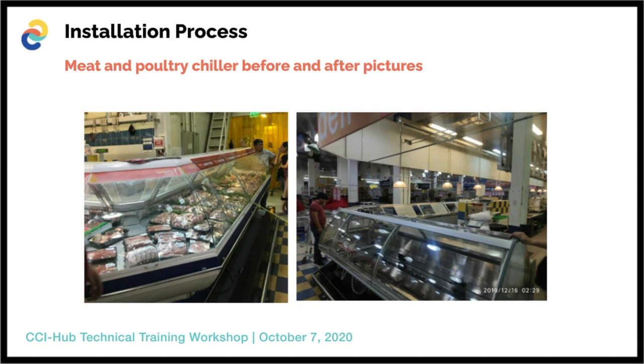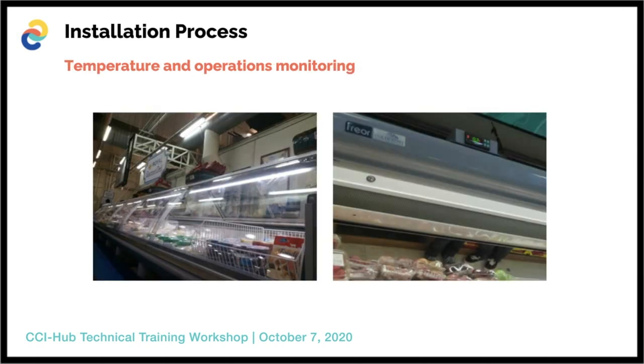So, temperature and operations monitoring. Before the morning opening of the store, we need to set the R290 showcase into the respective temperature range. As per experience, the average time needed for the showcase to reach the design temperature using the R290 system took only 1 to 2 hours, whereas the R404 system may take 3 to 4 hours. Since the showcase is loaded with products right after the testing, a monitoring personnel was on standby to check the overall operation and functionality of the system.